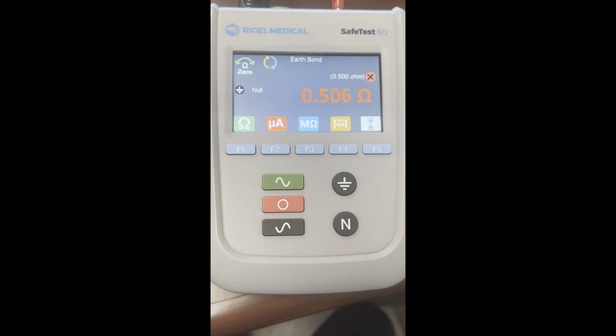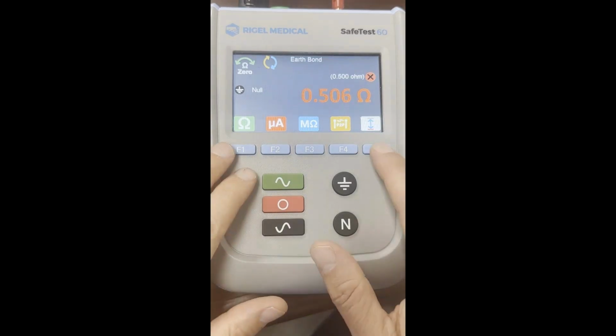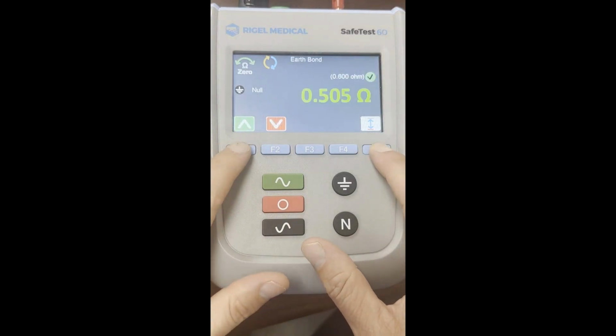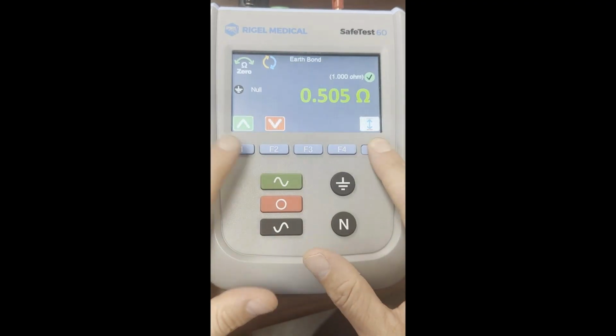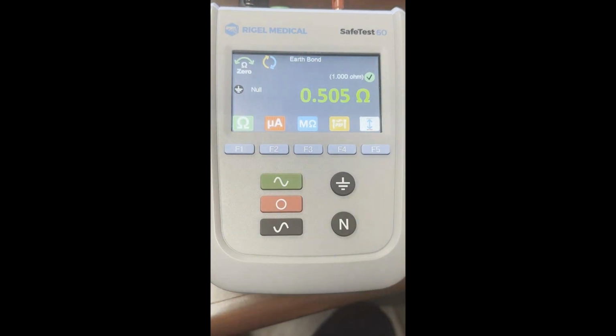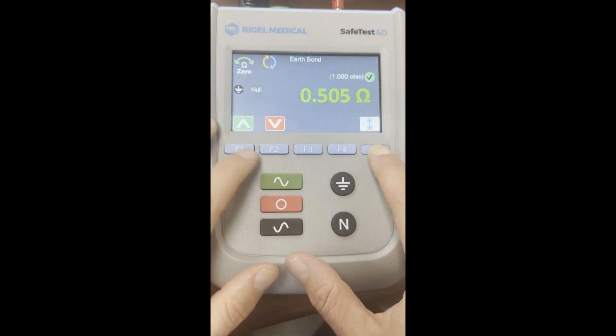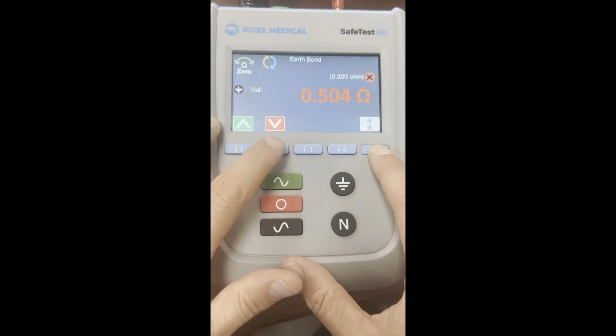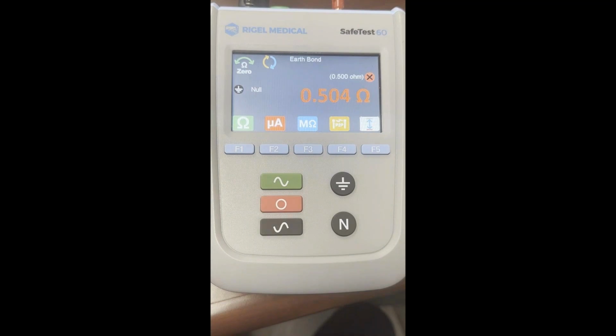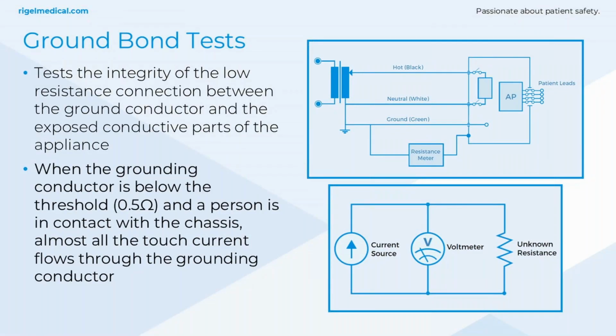What I'm doing here is just stepping up through the resistance values using a decade box. This is not actually a piece of test equipment. I'm just showing you how the feature works, whereby if it's below the pass/fail threshold, then it will indicate with a green tick and show that the values are correct. We go back to the standard 0.5. If it's above that value, you can see it shows up red. It's a very simple feature.